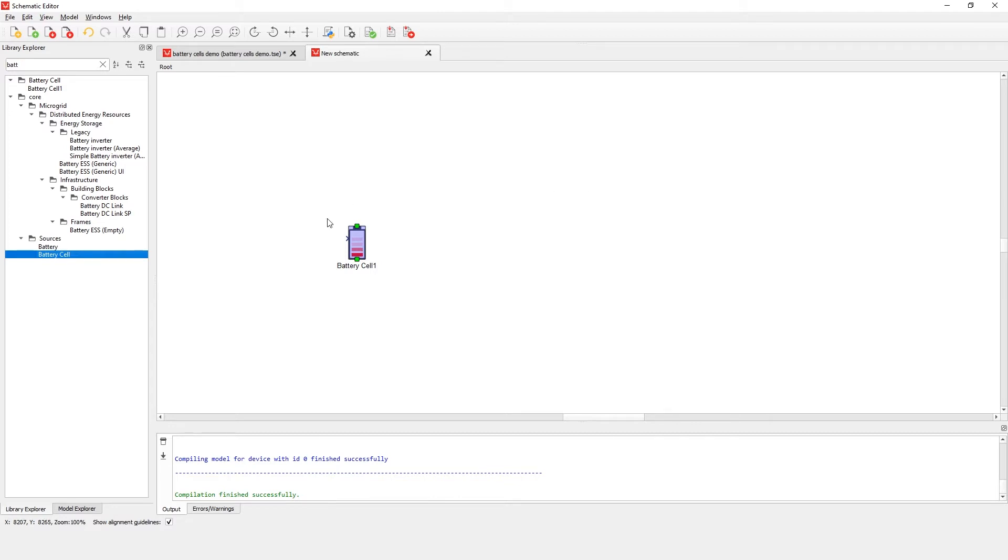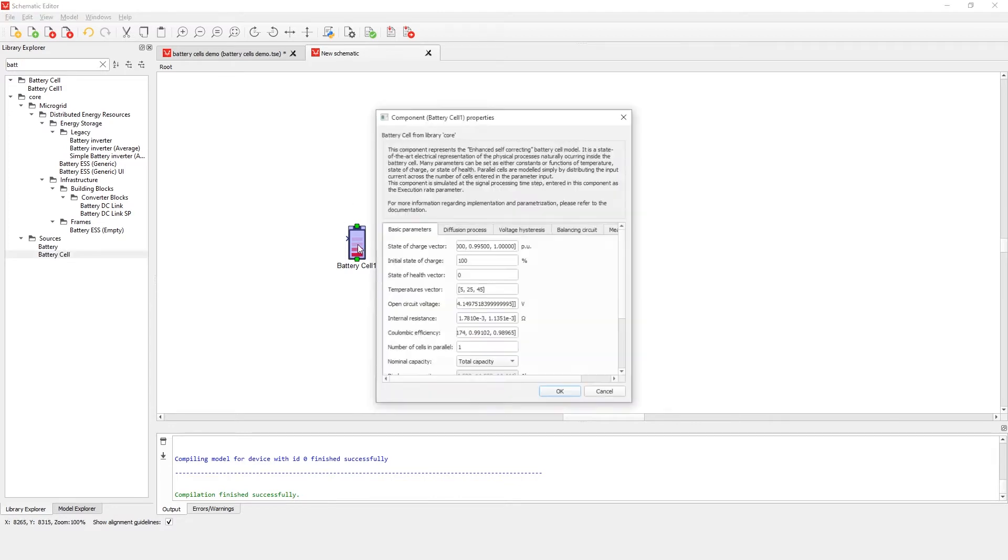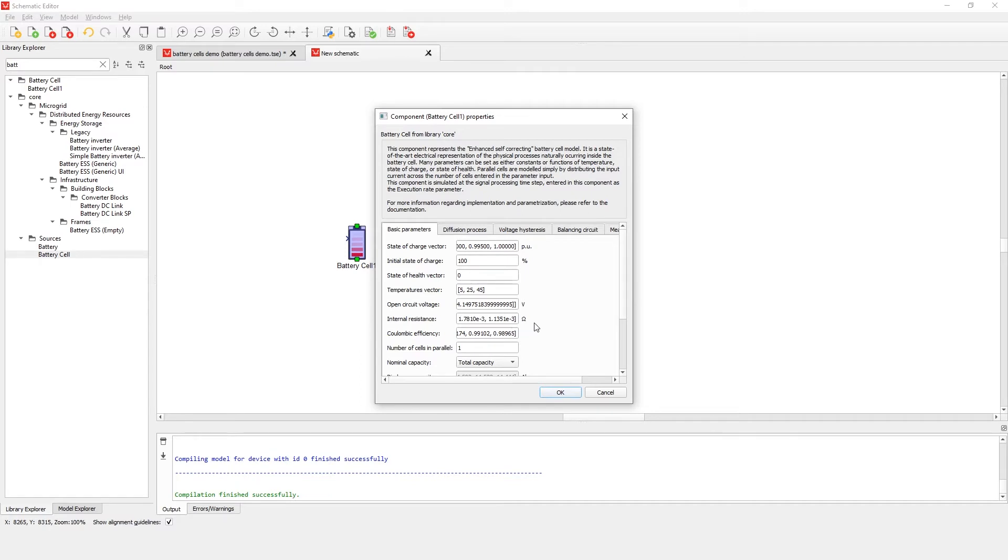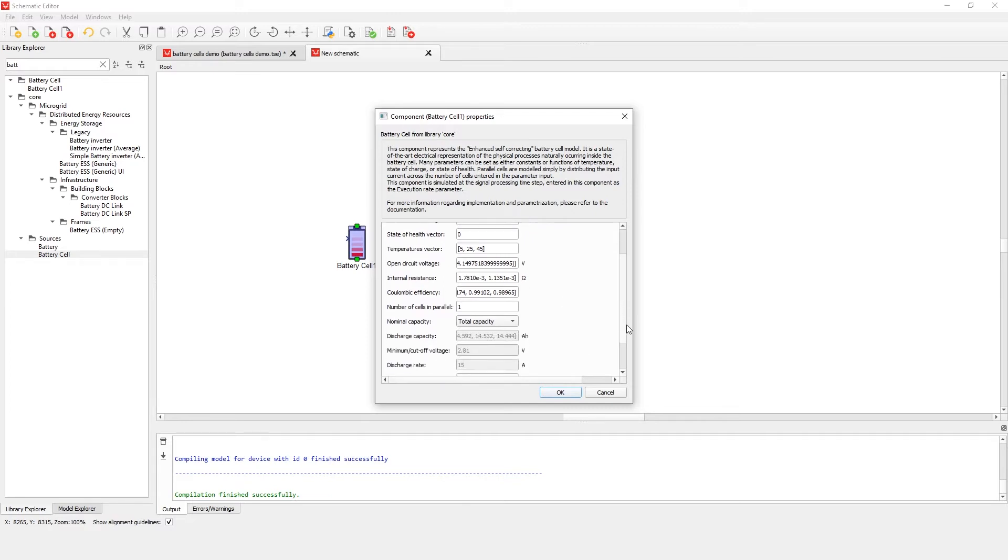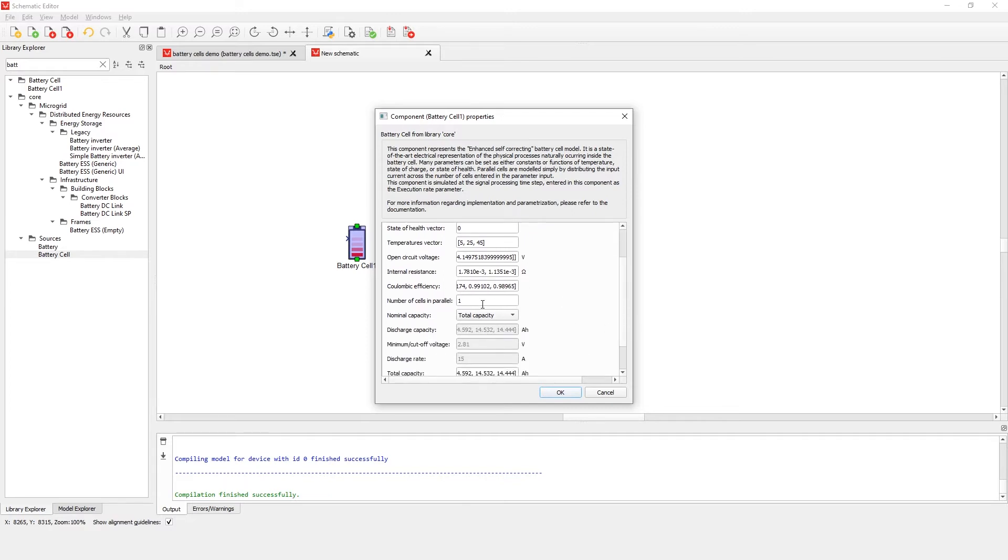By opening the component properties, you can see several tabs. In the basic parameters tab, you can define basic characteristics of the battery such as the state of charge vector, the initial state of charge, temperatures, state of health, open circuit voltage, and internal resistance. Within this tab, you are also able to define number of cells in parallel as well as the nominal capacity of the battery system under test.